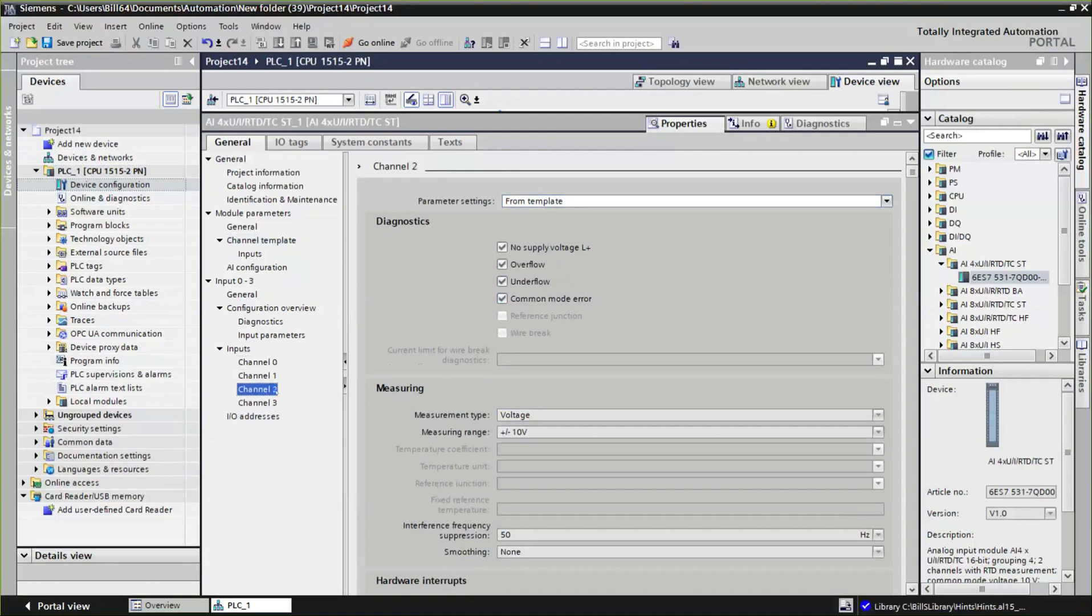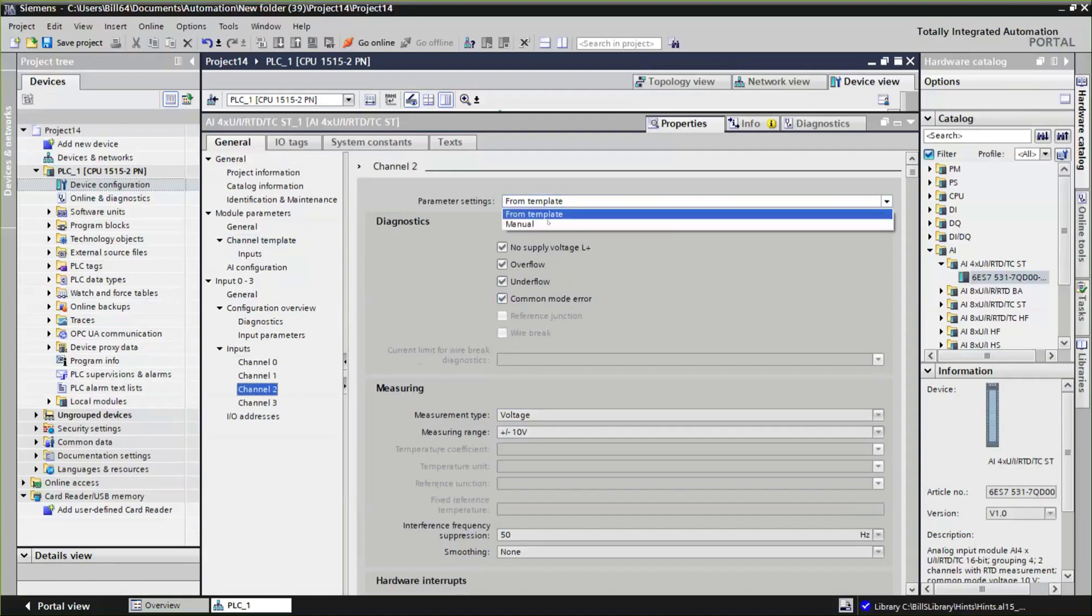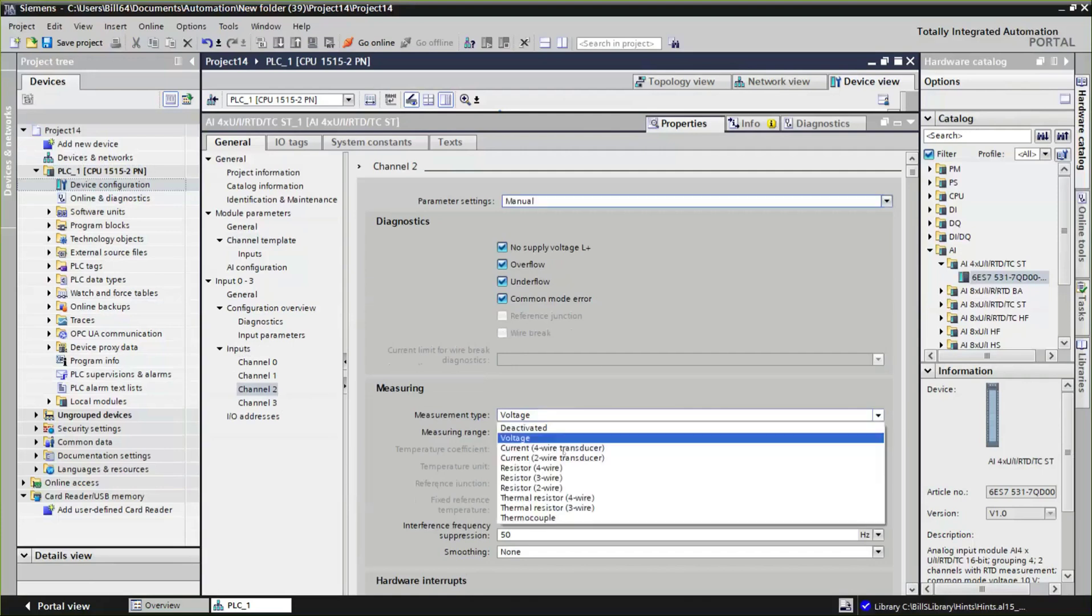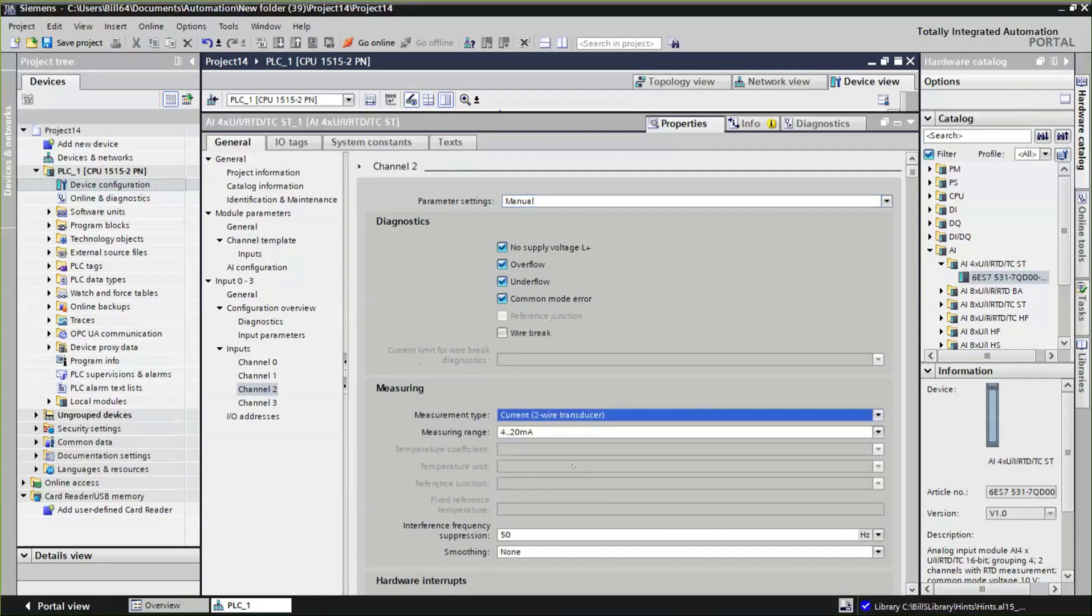But oftentimes, what we have are a mixed bag of signals. For example, if we have a standard configuration for a PLC that we want to actually use over and over again, we go ahead and configure that. I'll make the third and fourth channels of this analog input, make these four to 20 milliamp, for example. And with four to 20, we can check for wire break.